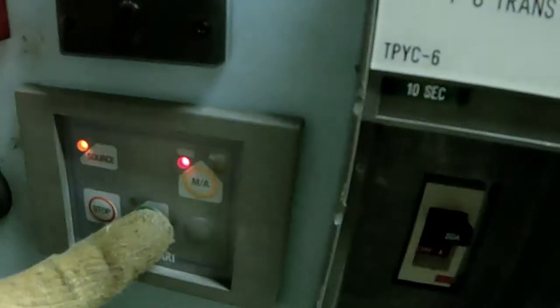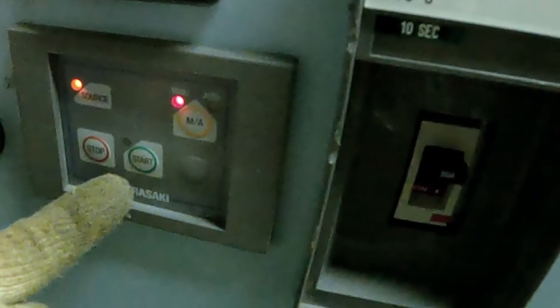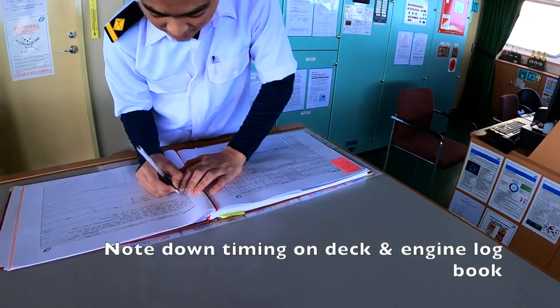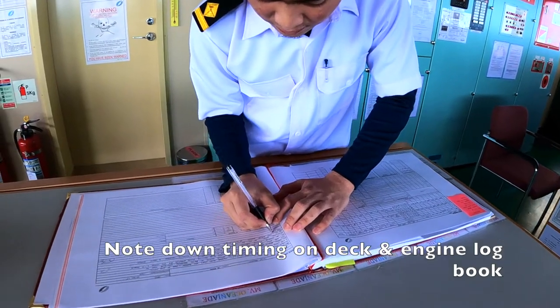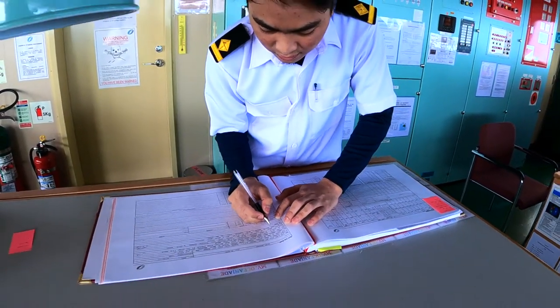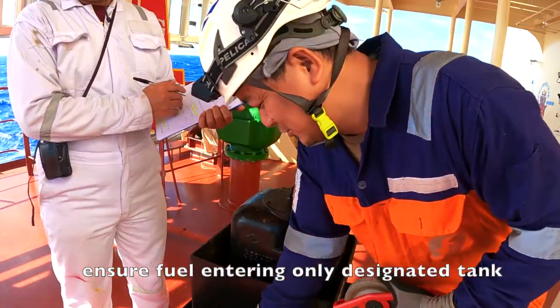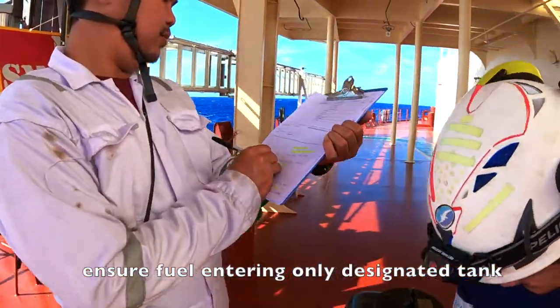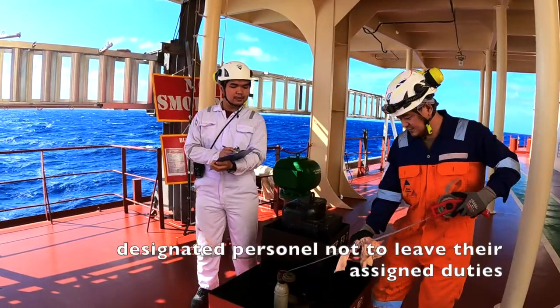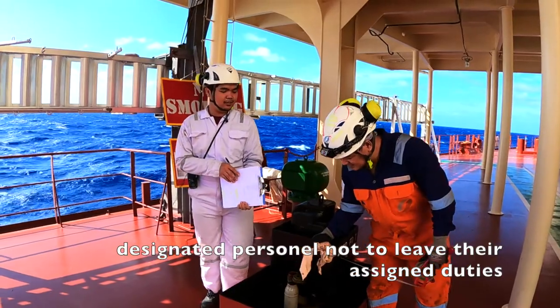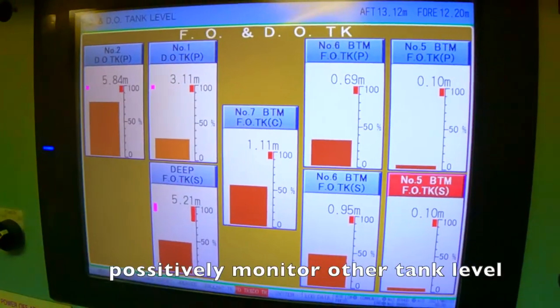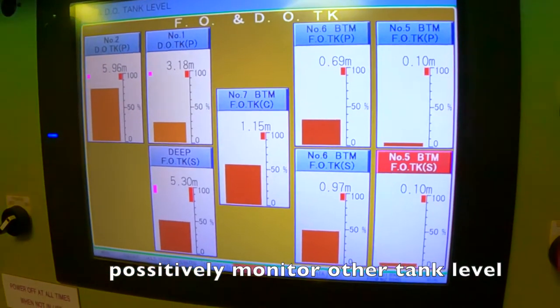Now start transfer pump from engine room and note down timing on deck and engine logbook. Ensure fuel is entering only the designated tank. Designated personnel not to leave their assigned duties and positions. Positively monitor other tank levels by display and manual sounding.